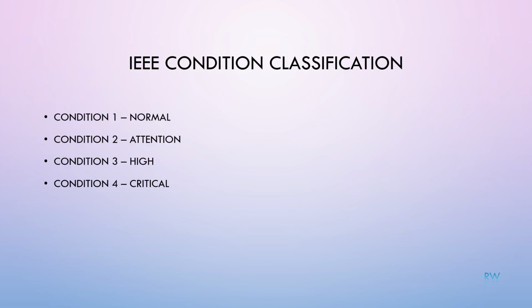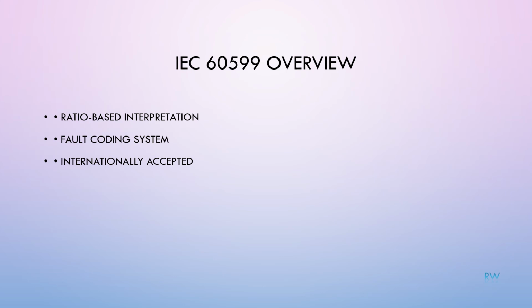Condition 1 means normal. Condition 2 indicates attention required. Condition 3 indicates high gas levels. Condition 4 indicates critical condition requiring urgent action. Actions depend on both level and trend. IEC 60599 focuses more on gas ratios and fault identification coding. It provides attention limits and structured interpretation tables. It is widely used internationally and considered strict in some parameters.